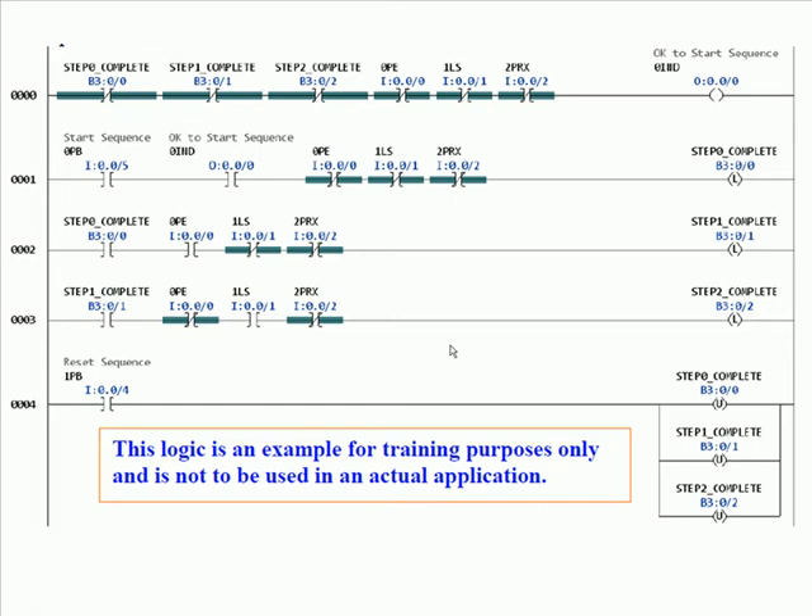When rung zero is true it turns on output zero — 'ok to start sequence.' If you look at rung 1, 'ok to start sequence' is preceded by 'start sequence,' so we have push button zero wired to input 5, ANDed with 'ok to start sequence,' ANDed with the same three conditions from rung zero: photo eye, limit switch 1, and prox 2. The output indicators — indicator zero — are probably a lit push button, so when the first rung is true it illuminates a lamp saying it's ok to start a sequence.